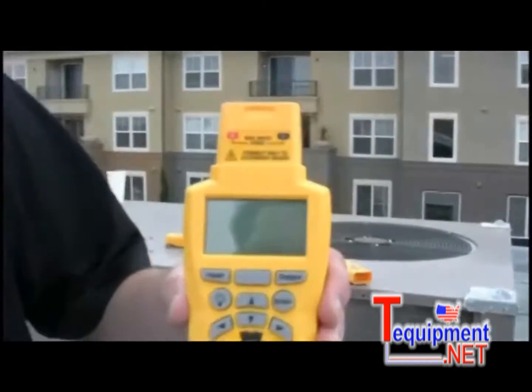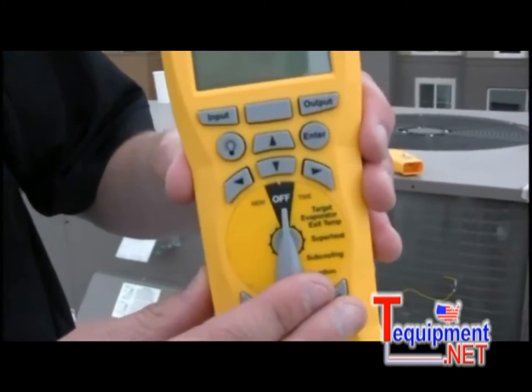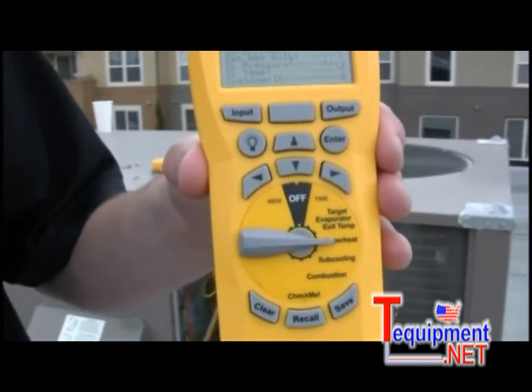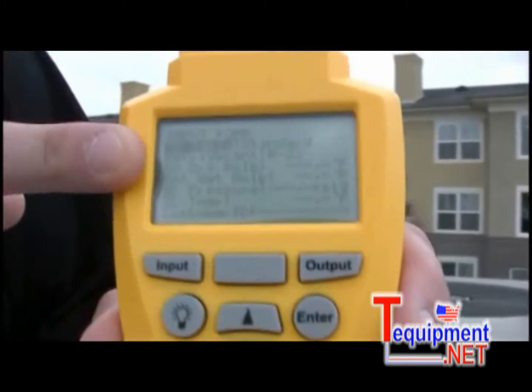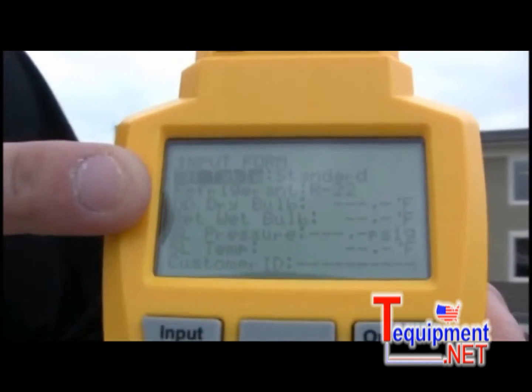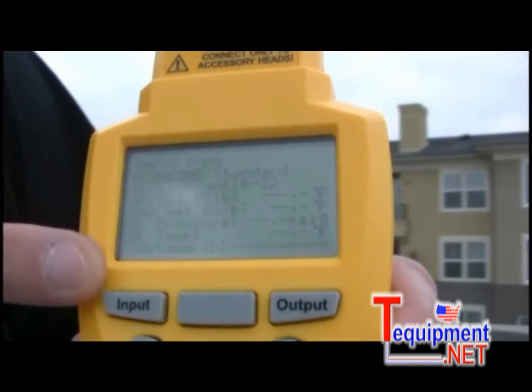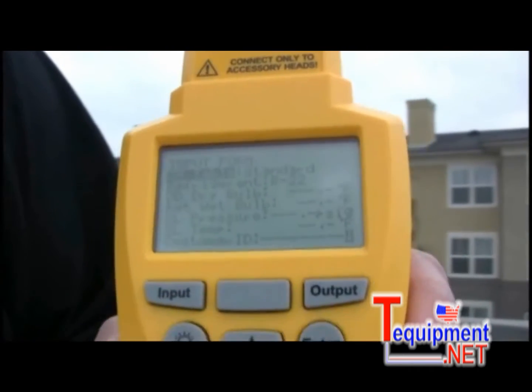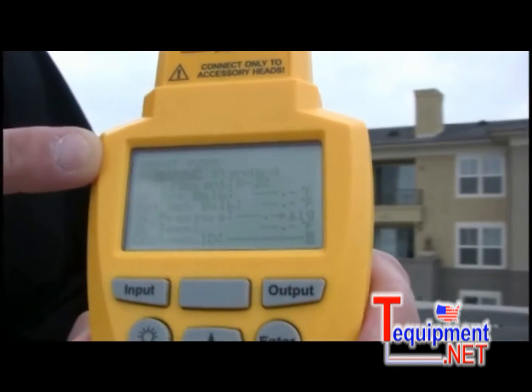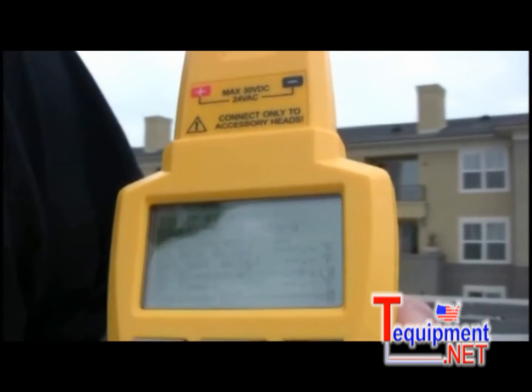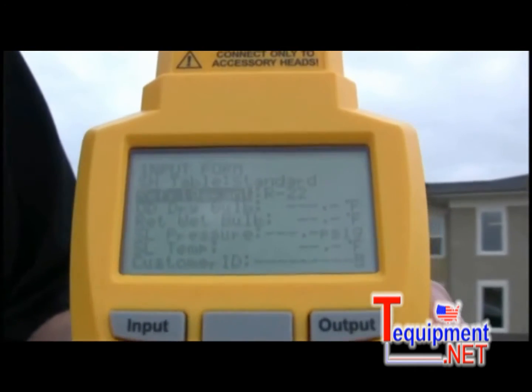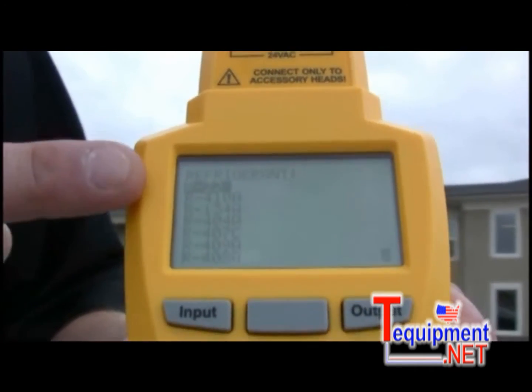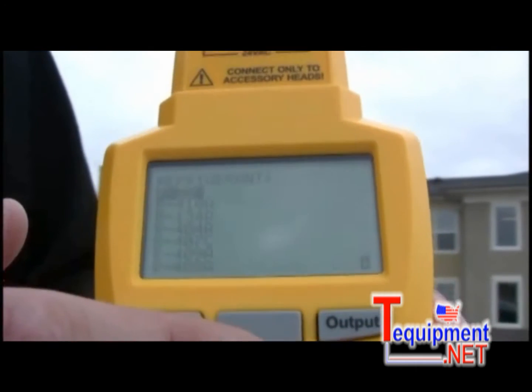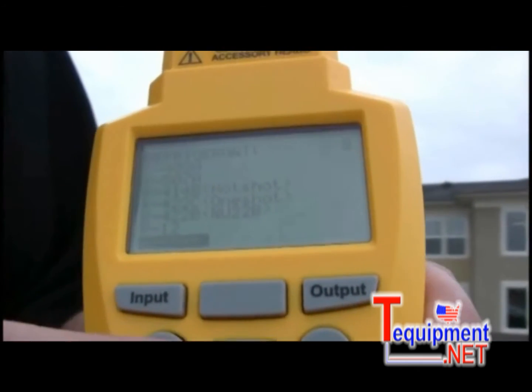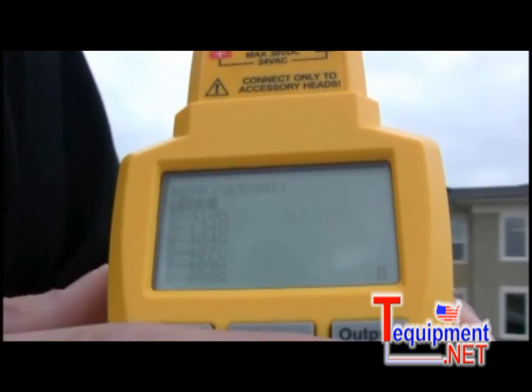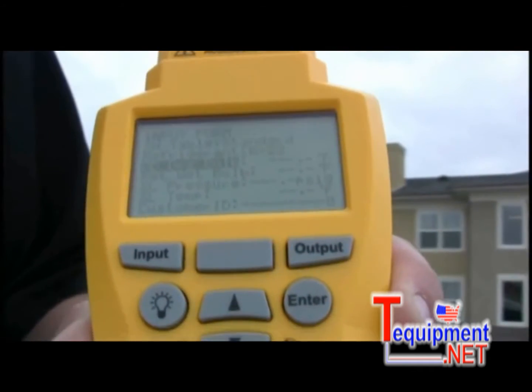So basically, how the HVAC Guide works is you select a test on the dial. So I'm going to select superheat. That brings you to the superheat input form on the screen. What we're basically going to do is go step by step and fill this screen out using all of our accessory heads. So the first thing I'm going to do is select our refrigerant. I'm going to press enter to get to the list of refrigerants just to show you what refrigerants we do have available. But I'm going to go ahead and select R22 because we're on the R22 system.